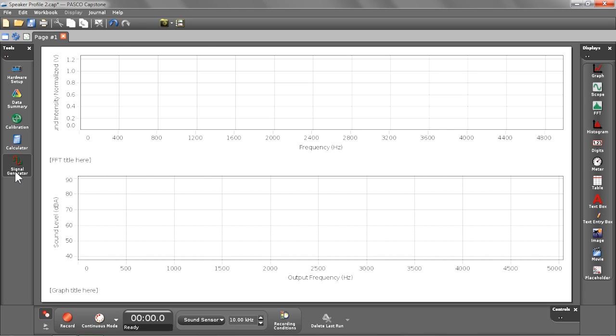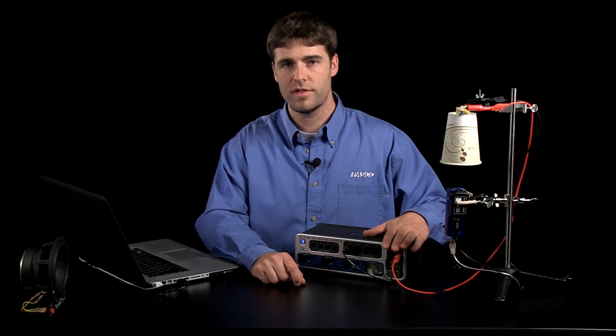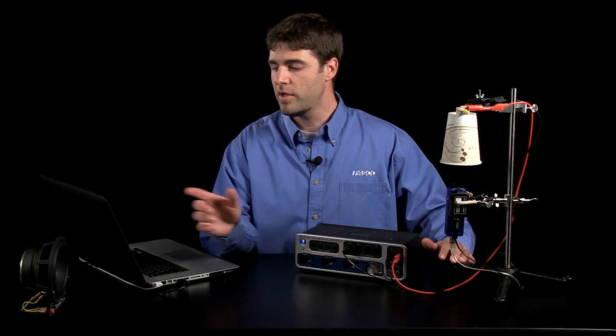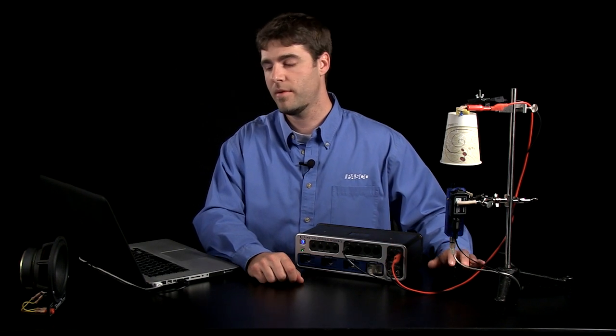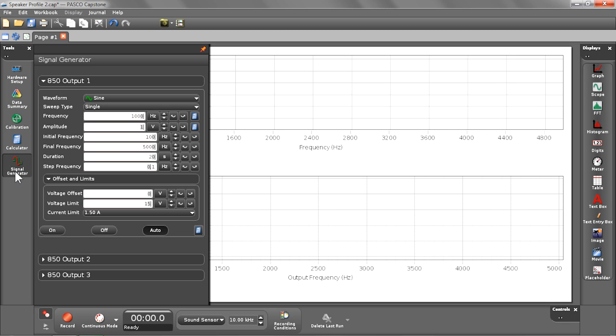As I mentioned we'll be driving the speaker using the output function generator on the 850. So let me go ahead and explain the controls that I have set up already. As you can see we'll be driving the speaker using a one volt sine wave and we'll be sweeping through a band of frequencies starting at 100 hertz and ending at 5 kilohertz. The sweep should take 20 seconds and the step frequency should be 0.1 hertz.